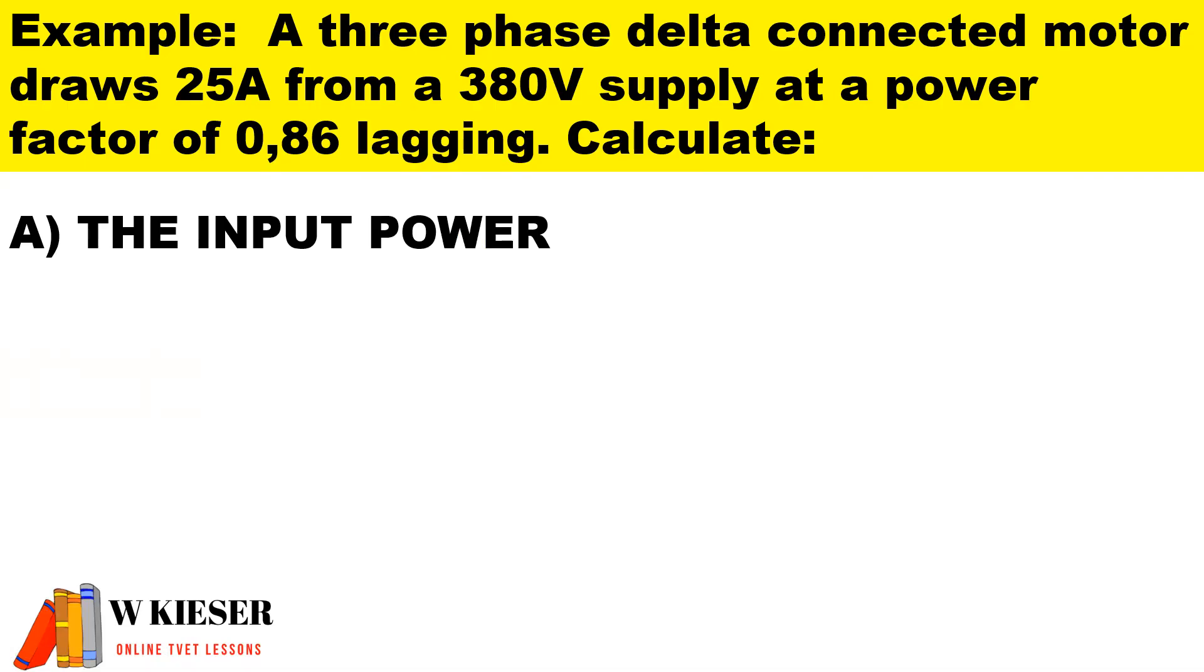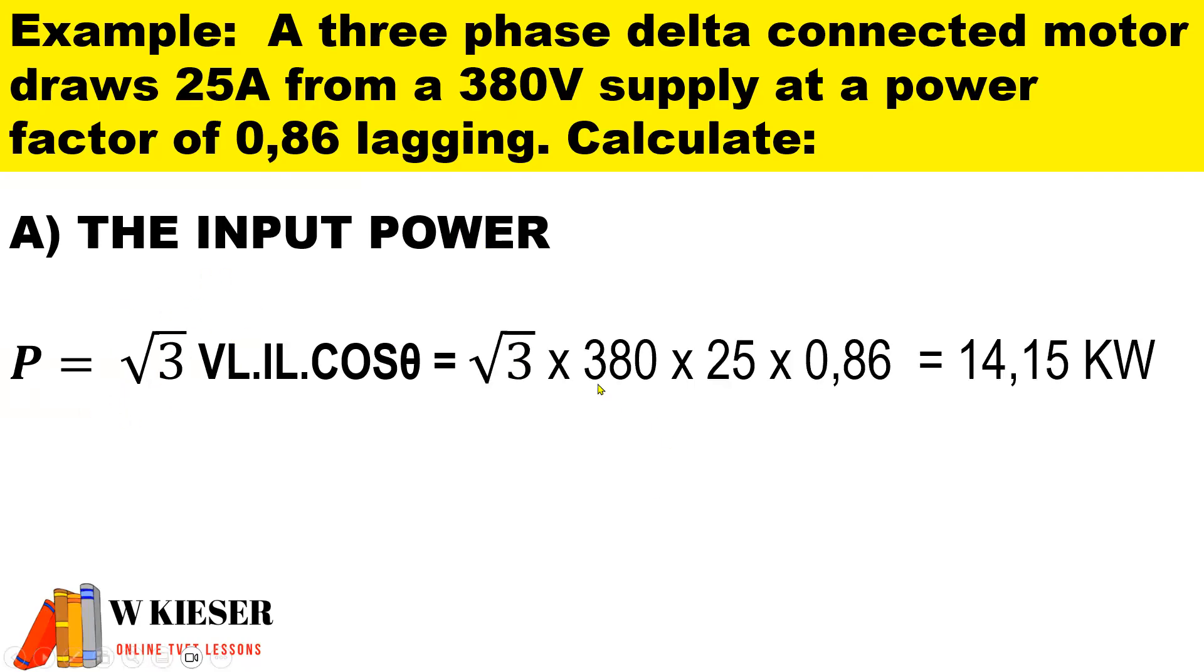To calculate the input power, the formula for power for a three phase circuit we multiply by square root 3. So therefore the line voltage is 380 volts, the line current is 25 amps, and the power factor is 0.86. This gives us 14.15 kilowatts.